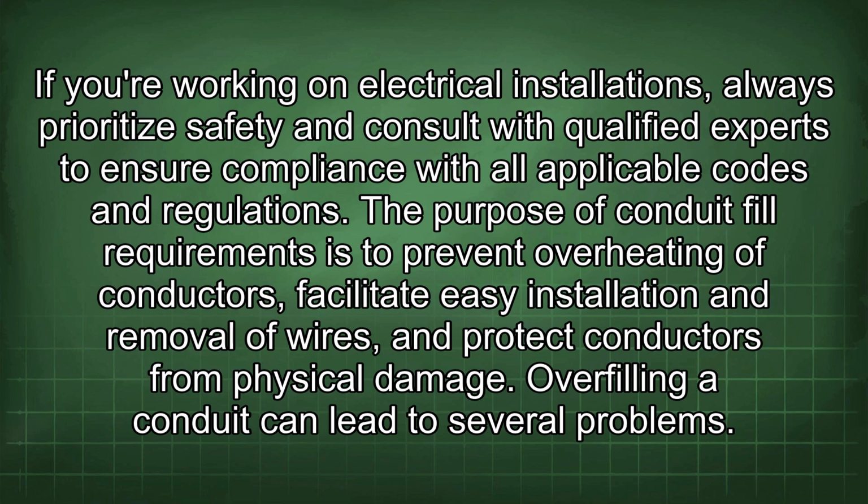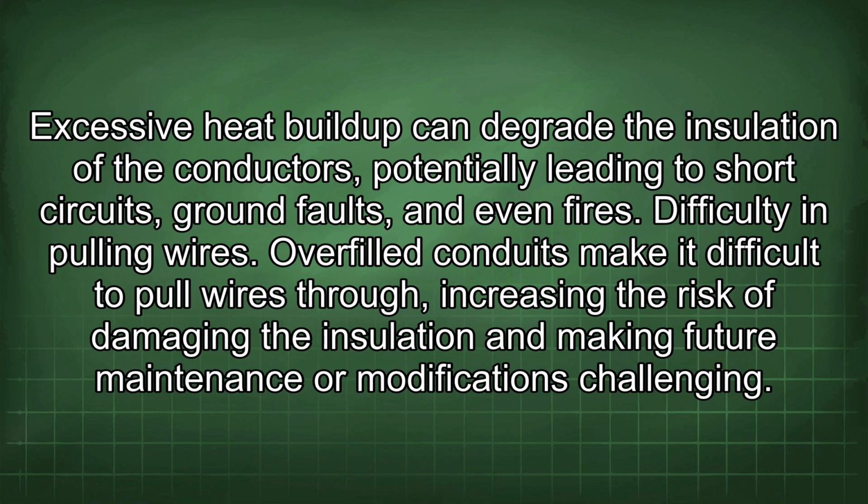The purpose of conduit fill requirements is to prevent overheating of conductors, facilitate easy installation and removal of wires, and protect conductors from physical damage. Overfilling a conduit can lead to several problems. Excessive heat buildup can degrade the insulation of the conductors, potentially leading to short circuits, ground faults, and even fires.